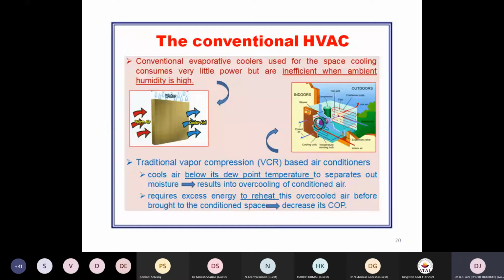They may be leaking faulty water from the drain pipe. That water is not from outside, but internally condensed water in the process of removing the humidity. So one of the great limitations of the vapor compression system is how the humidity can be removed. In the process, we may need a great compression ratio at the compressor and a very low evaporating point at the evaporator to maintain the surface cold temperature around 5 to 10 degrees to remove the water vapor in the form of condensed water.